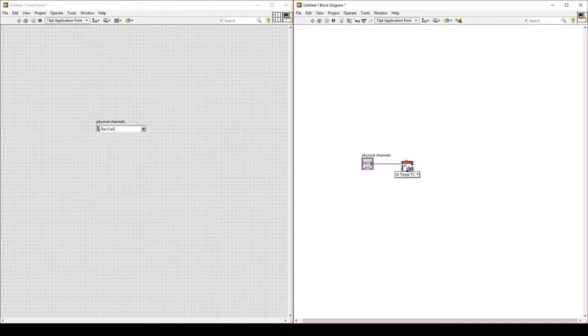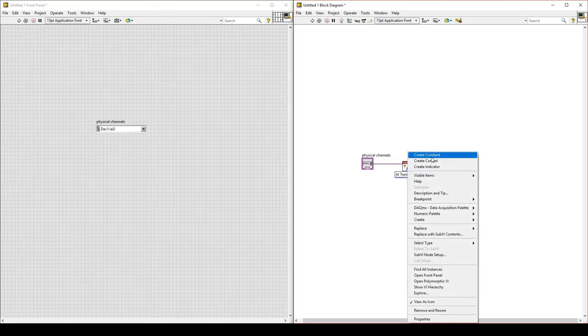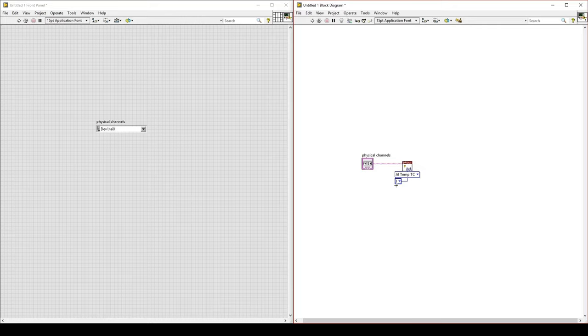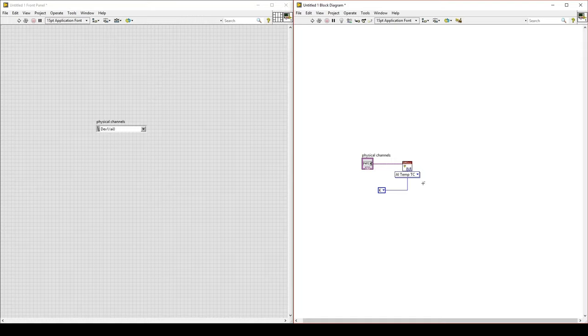On the Create Channel VI, at the bottom, there is a node called Thermocouple Type. Right-click on that node and create a constant. We are changing the thermocouple type from J to K type. Remember, the thermocouple type depends on the material the thermocouple is made out of, and that will affect the voltage output for a temperature measurement.